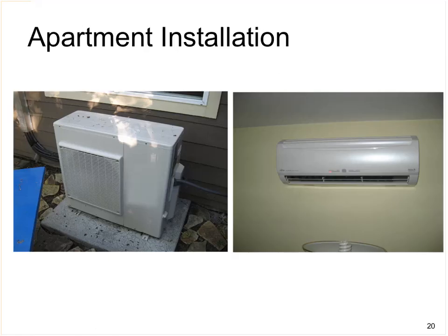So here are a couple of photographs of an apartment installation. One of the things I wanted to point out on this installation, and I'll use my arrow here, you can kind of see the edge of my green arrow, but this is the cover. On the outdoor unit to the left, you can see the refrigerant lines, the black lines going up the wall. And then you can see there's this cover that's been painted the same color as the house and looks like a gutter downspout. You can't tell it's there. It looks like the unit's installed on a pad designed to support the unit, and then on some sort of pavers or something. And on the right-hand side, we just have the indoor unit, just to give you a sense of what it looks like.